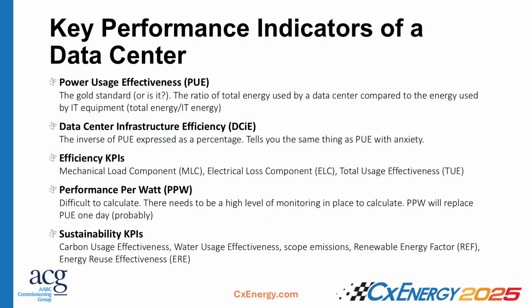However, in existing data centers, PUE can be pretty high, and I'll get to that in a moment. Another key performance indicator the IT team likes to focus on is data center infrastructure efficiency, DCIE. It's the inverse of PUE, expressed as a percentage. I like to say it tells you the same thing as PUE but with a side of anxiety, because as a percentage, say you're at 90%, if you add more load to the data center and that increases your PUE, it's going to decrease your DCIE. So you could go from 93% to 85%. That metric is used, but I don't particularly like it.